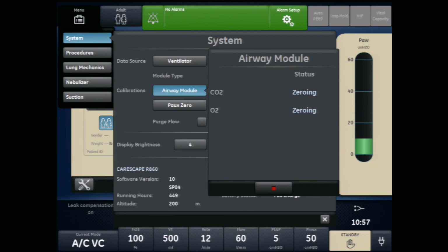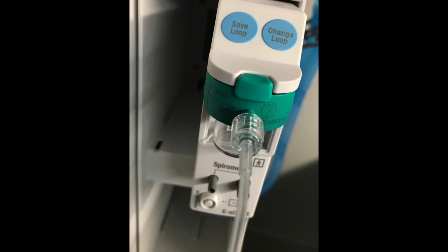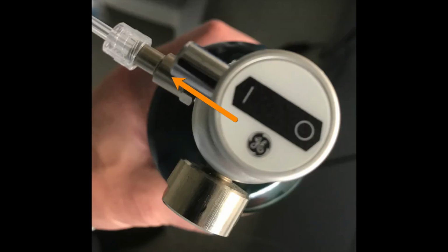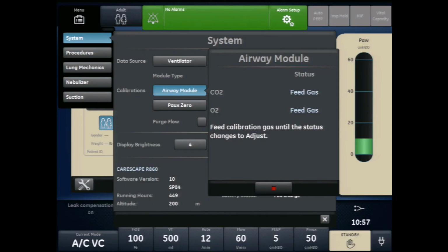The first part is the zeroing of the airway module. After the airway module zeros, the ventilator will ask you to feed the calibration gas. At this time, attach the gas sampling line to the airway module water trap and to the regulator. Turn the regulator on to feed the gas by pushing the pin to the 1 position. Feed the calibration gas until the message OK or Adjust displays on the screen.